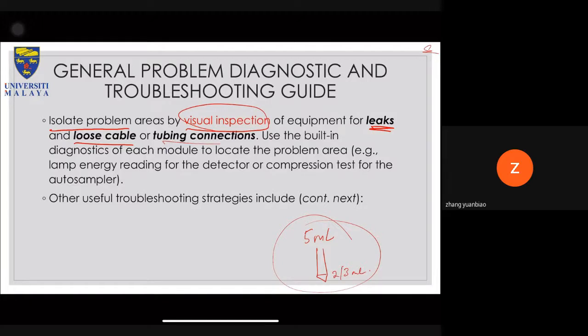Okay, so by looking at this by visual inspection of each module, you might be able to identify a problem that is caused by either pressure drop, pressure too high, or the flow being very low. Even if you see a wet working bench or wet floor, you might be able to find the cause of the mishap.